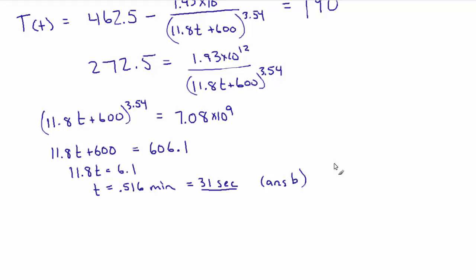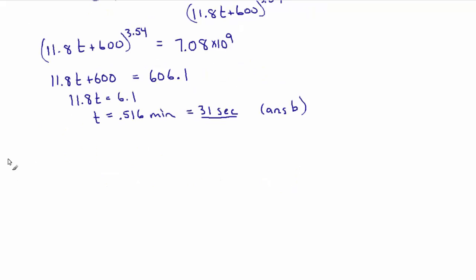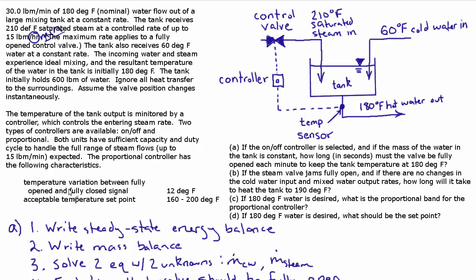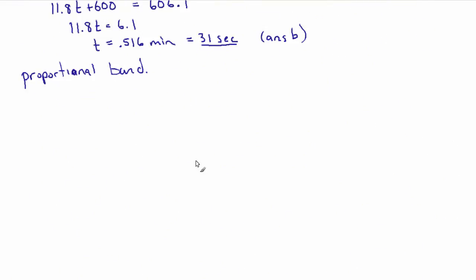Let's close out with Parts C and D. For Part C, they want to know the proportional band. In simple terms, the proportional band is the size of the range of temperatures through which the valve strokes — from fully open to fully closed. We were told the temperature variation between the fully-open and fully-closed signal is 12 degrees, so the proportional band is 12 degrees Fahrenheit.